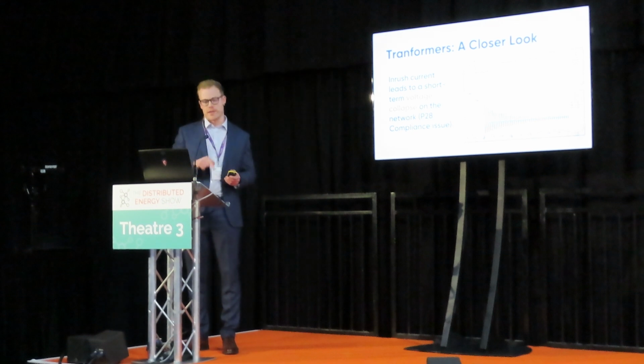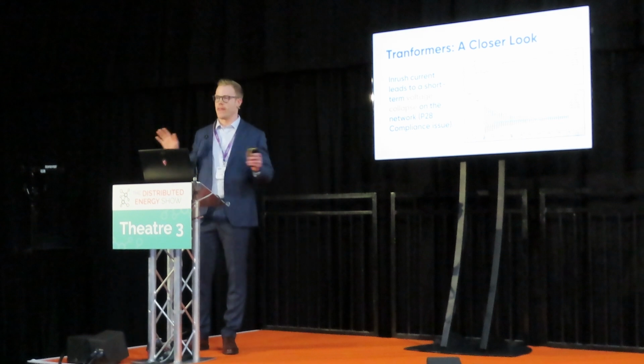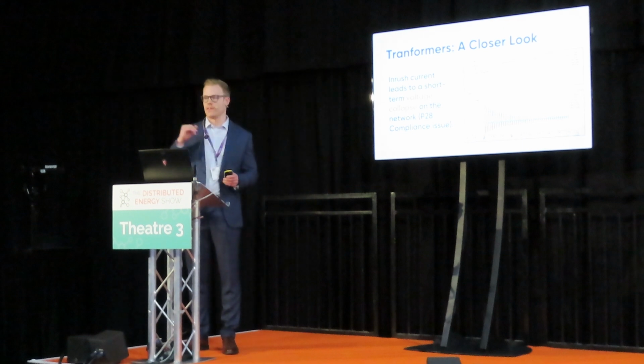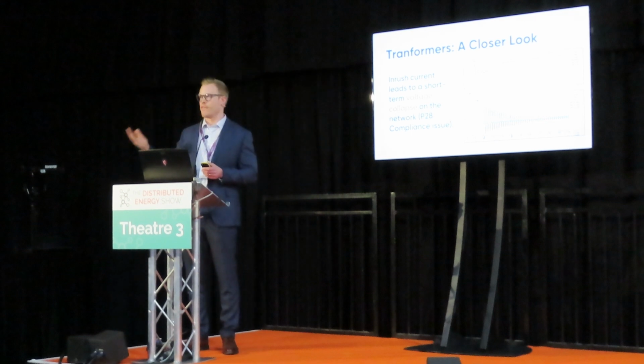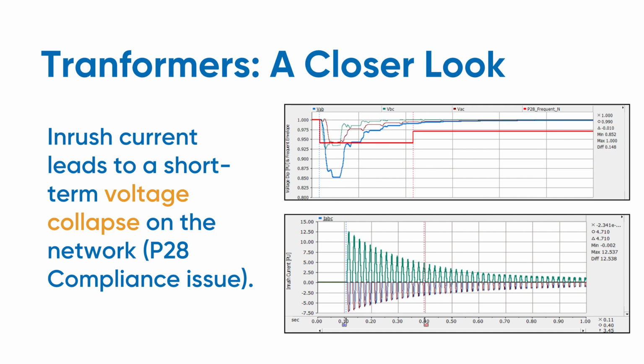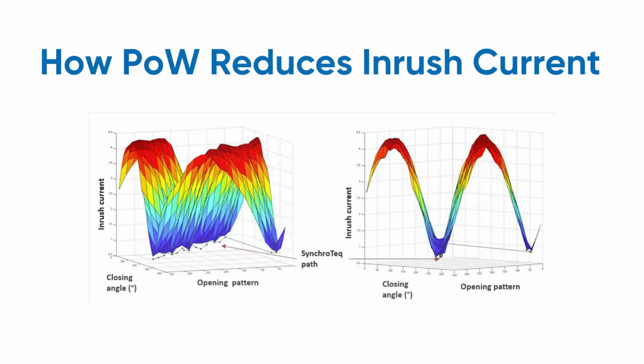Now, imagine we just let that go unchecked and we were creating these voltage collapses all over the network whenever we switched a transformer. We'd have a very poor quality supply. We'd have flickering, we'd have loads tripping, we'd have loads damaging. And if we completely left this unchecked, it would lead to massive grid instability and potential blackouts. So this is the common reason that we're interested, and it's a problem when we're energizing transformers in weak networks.